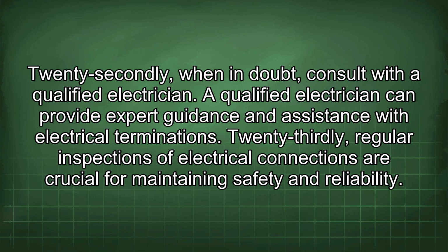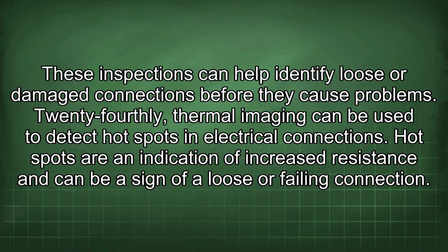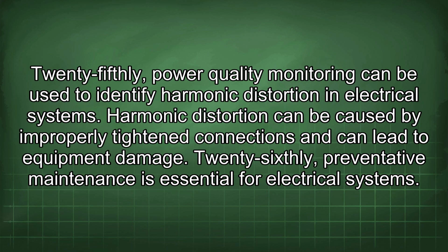23rdly, regular inspections of electrical connections are crucial for maintaining safety and reliability. These inspections can help identify loose or damaged connections before they cause problems. 24thly, thermal imaging can be used to detect hot spots in electrical connections. Hot spots are an indication of increased resistance and can be a sign of a loose or failing connection. 25thly, power quality monitoring can be used to identify harmonic distortion in electrical systems. Harmonic distortion can be caused by improperly tightened connections and can lead to equipment damage.